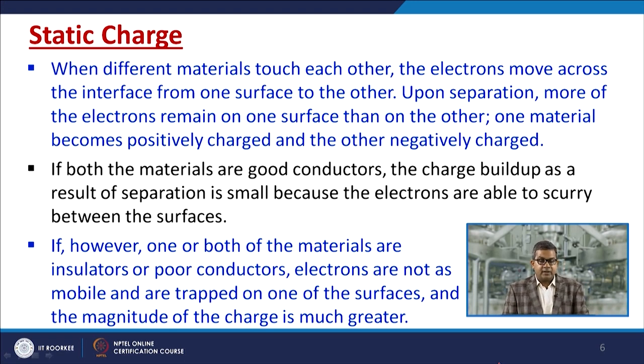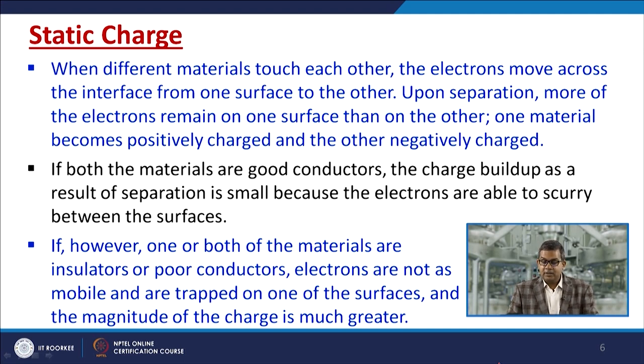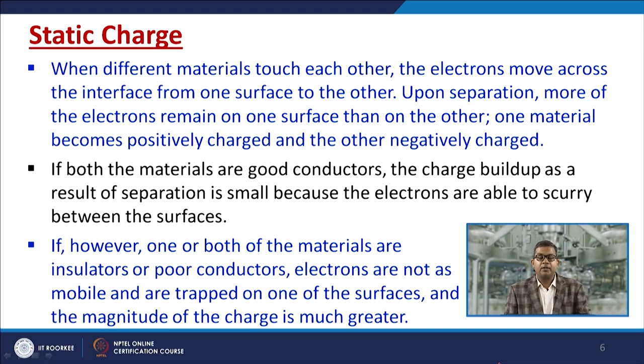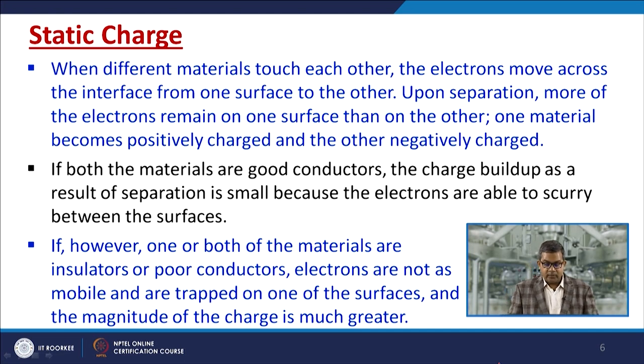When different materials touch each other, electrons move across the interface from one surface to the other. Upon separation, more electrons remain on one surface, so one material becomes positively charged and the other negatively charged. If both materials are good conductors, charge build-up is small because electrons can move freely between surfaces. If one or both materials are insulators or poor conductors, electrons are trapped and the magnitude of charge is much greater, producing higher-intensity sparks or arcs.